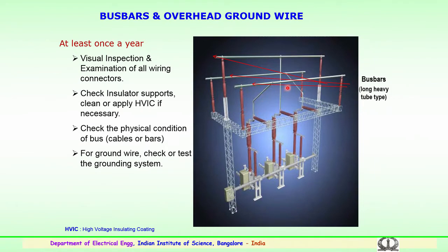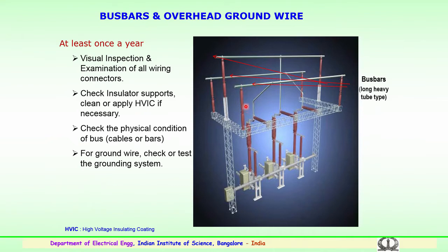Bus bars are long heavy tubular structures in any substation — these bus bars are overhead structures. At least once a year, a visible inspection is to be carried out at regular intervals, examining all the wiring connections connected to the bus bar and the end connections. It has to be properly checked whether the insulator supports — which may be of pedestal or long rod type — have contamination or deposits on the insulator surface, which have to be cleaned at regular intervals. If necessary, a suitable high voltage insulating coating has to be applied.